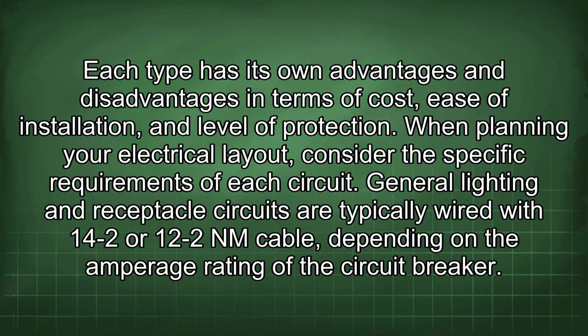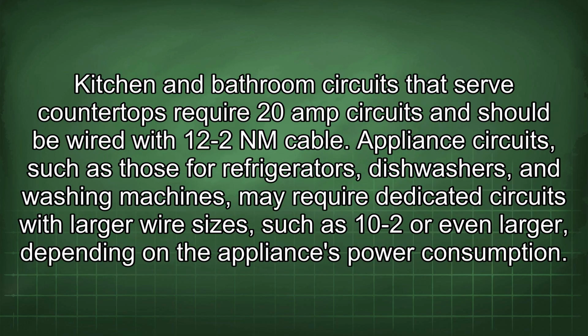When planning your electrical layout, consider the specific requirements of each circuit. General lighting and receptacle circuits are typically wired with 14-2 or 12-2 NM cable, depending on the amperage rating of the circuit breaker. Kitchen and bathroom circuits that serve countertops require 20 amp circuits and should be wired with 12-2 NM cable. Appliance circuits, such as those for refrigerators, dishwashers, and washing machines, may require dedicated circuits with larger wire sizes, such as 10-2 or even larger, depending on the appliance's power consumption.